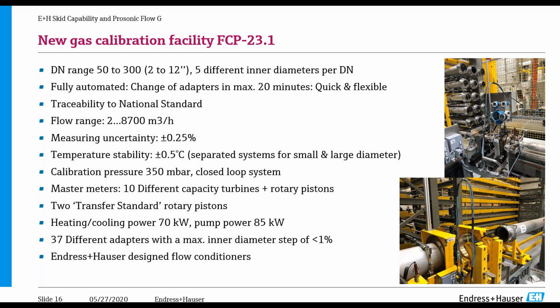We can go higher than that, all the way up to about 60, 65 meters a second. The problem is the stability. So right now we specify at 40 meters per second. And most importantly, the measuring uncertainty of this gas calibration rig is 0.25%. And this is all traceable. We use a system of turbines and positive displacement rotary pistons to keep it to national standards.